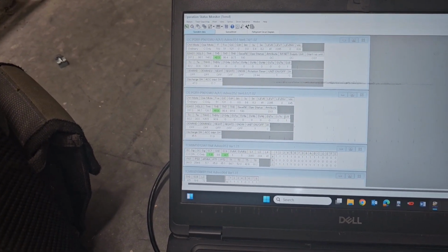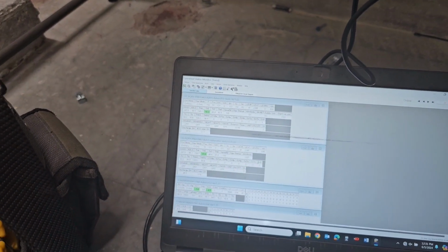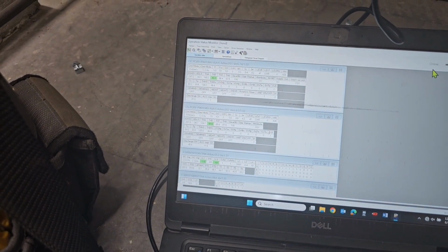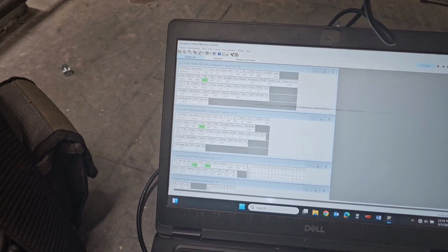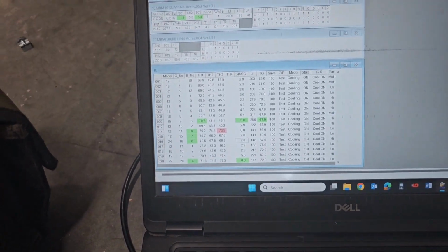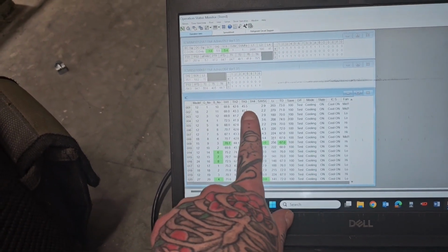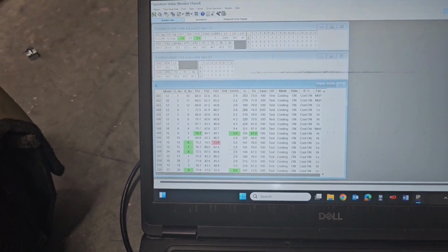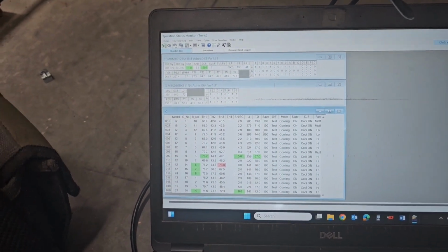There's no way you can have high superheat at your indoor units, high superheat at your branch controller, but yet you have no superheat at your outdoor units. The only case you'd see that is in a case like right now, when we don't have much load on our fan coils. I mean, everything entering 42, leaving 45, there's not much load on these systems. It's been running for almost 2 hours now in test mode.